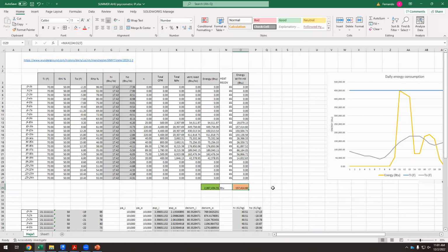Our clients will get cold there because we can never get the power that we need. And what happens when we have a huge boiler, much bigger than what we need? If we have this cycle, that is harmful. So that damages the boiler. So we need something that is above the requirements, but not too much, so that this cycle is repeated every 2 hours instead of every 5 minutes. Again, common sense. And we're not going to decide that, okay?